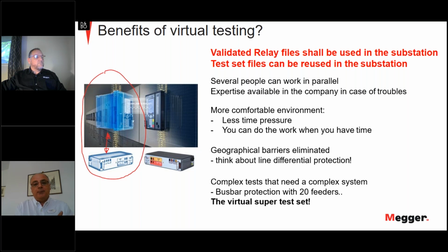All of this is important because when you do these tests, you validate your software, the relay settings, the relay configuration, and the relay files can be used in the substation. Also, the relay test set files saved can be used in the substation when I connect to the physical test set. So when you are in the substation and commissioning, you know that things should already work because you tested them in the digital twin in the virtual world.